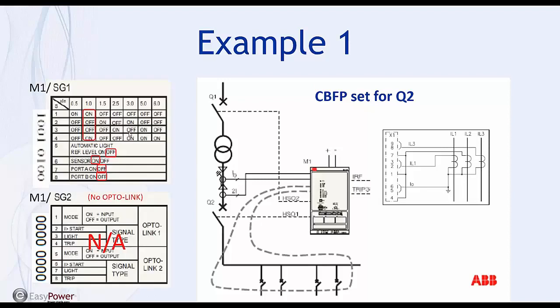Here's M1, which is the main unit. That's all we have here. We're going to set a 1 amp pickup and per unit of the nominal. Don't need backlight compensation in this case. We're going to activate the sensor, and the ports are off. We're not connecting any extension units, so both of those are off. We're also not connecting an opto link to pass current or trip or light information, so this is not applicable either.